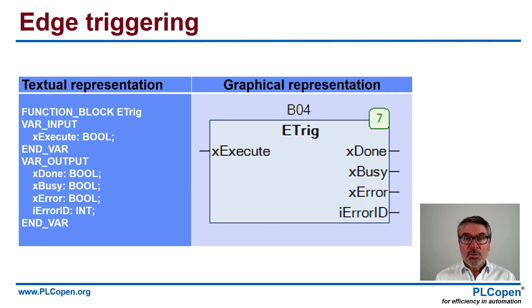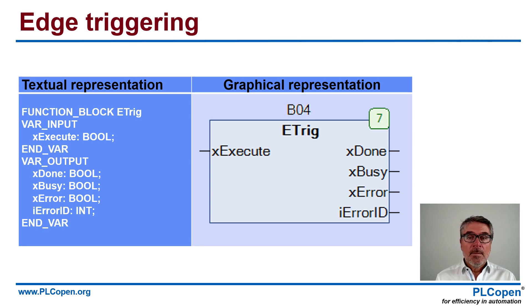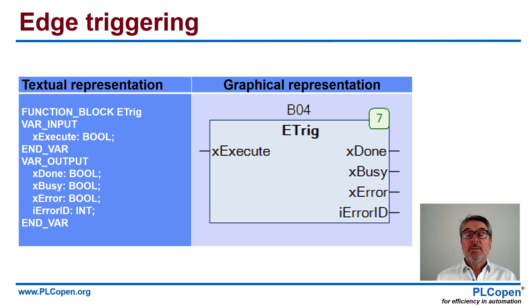Let us look at the first one: edge-triggering. Here you see on the left the textual representation and on the right the graphical representation. The rising edge executes and starts the function block, and you will see that at the busy output. When it is done with its work, the done output will be set — if there is no error, with no accompanying error indicated.